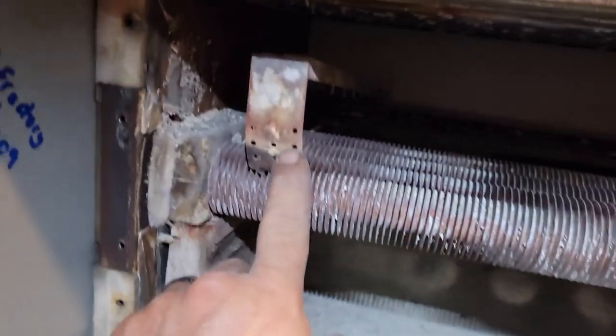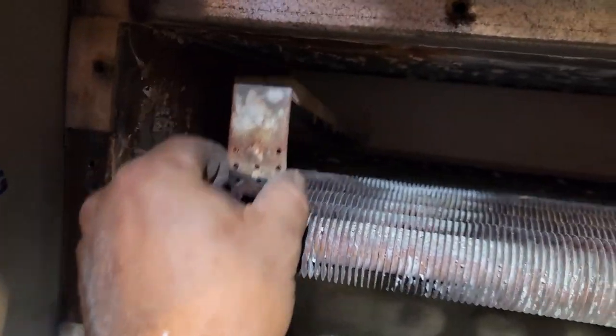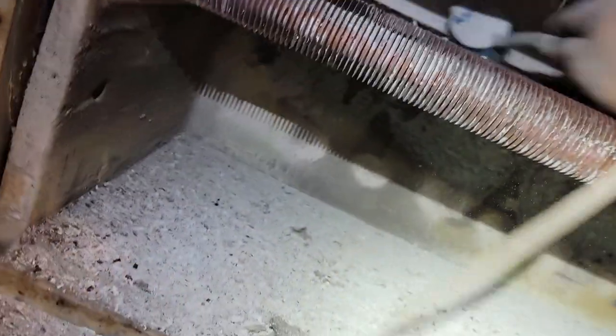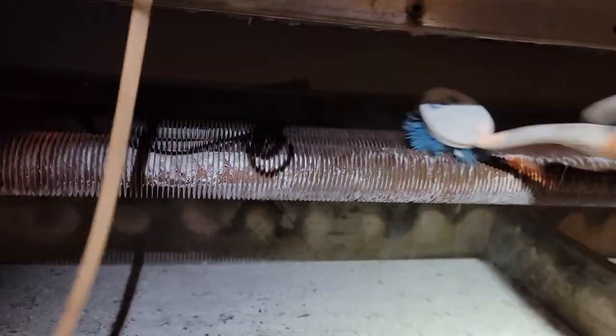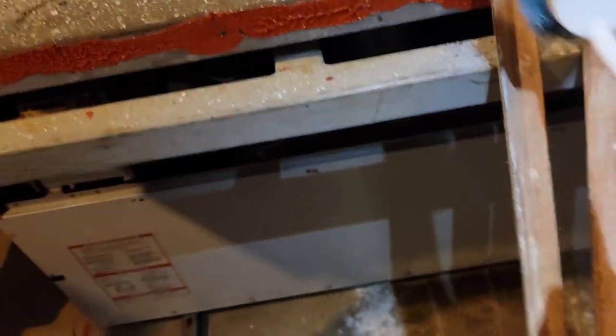This should run a little bit better. These are the restrictor plates on top of the burners. We really needed to get in between there. We got a good majority of it out, but for the most part I gotta admit this is a really nice design. You never get into it that quick or easy. I've always worked on more McLean and Burnham boilers than anything else, but Lochinvar seems to be what I see the most in the bigger buildings.